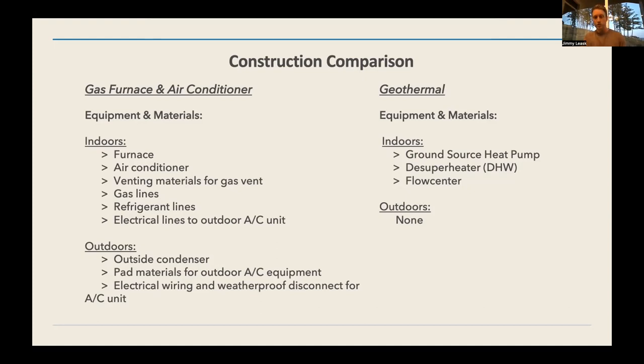Whereas with a geothermal system, inside you just have one ground source heat pump in one box that does your heating and cooling. It does have the ability to add a desuperheater, which can supplement your domestic hot water, and a small pump or flow center within your mechanical room that connects the ground loop to the heat pump. That's it—there's no outdoor equipment. All of the infrastructure is buried underground, which is wonderful, so you get to eliminate a lot of that outdoor nuisance.